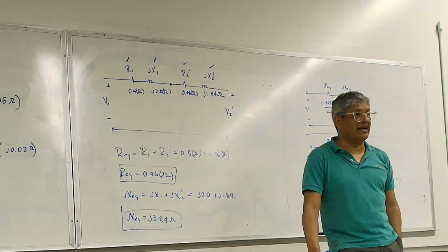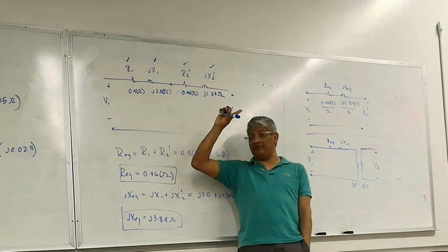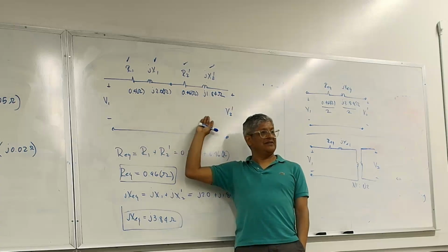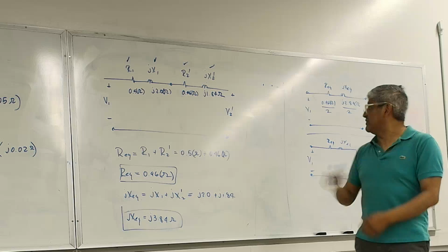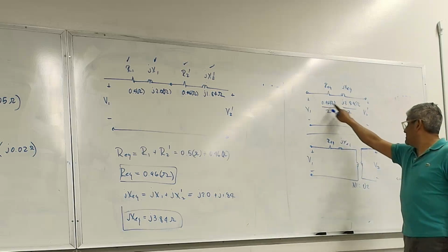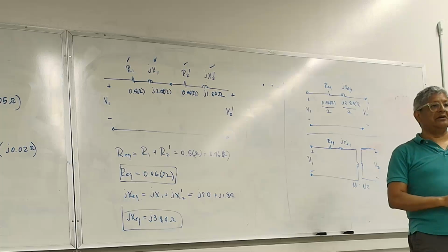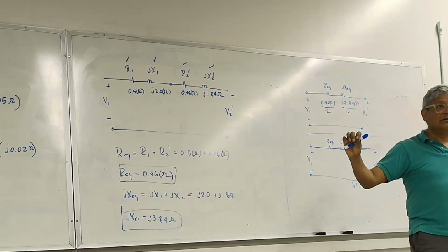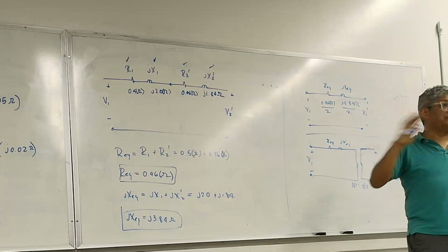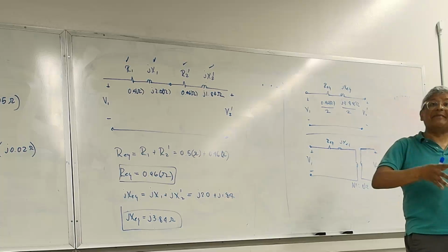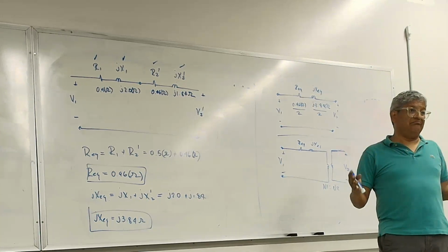So they do testing, and basically they go and measure these values. That's one of them. They have equipment, they plug it in, boom, and it gives you this value and this value. It can also give you the hysteresis, because the hysteresis can tell you a lot. Hot spots. There's a lot of stuff, but there is some maintenance associated with those.